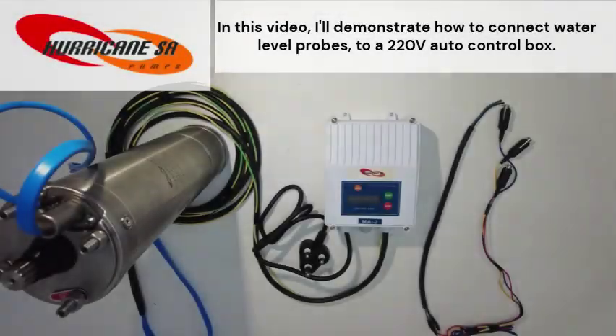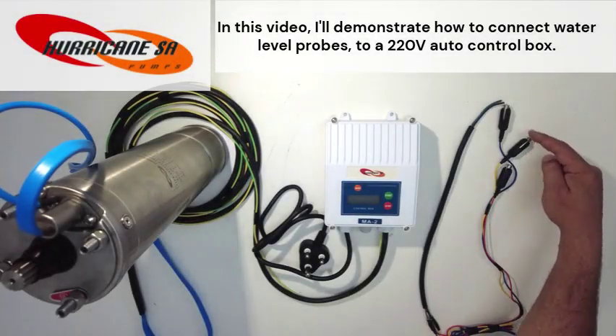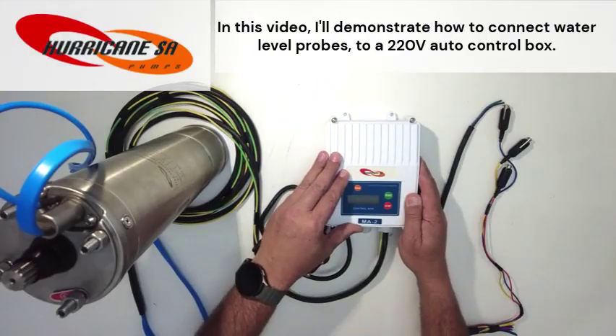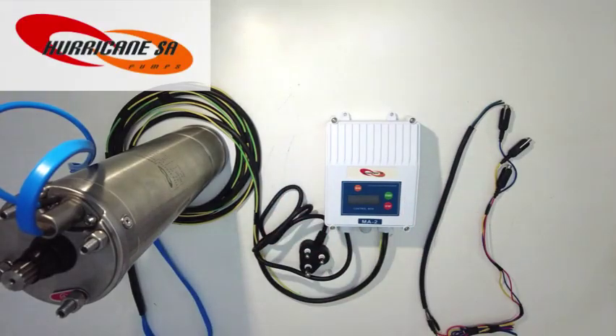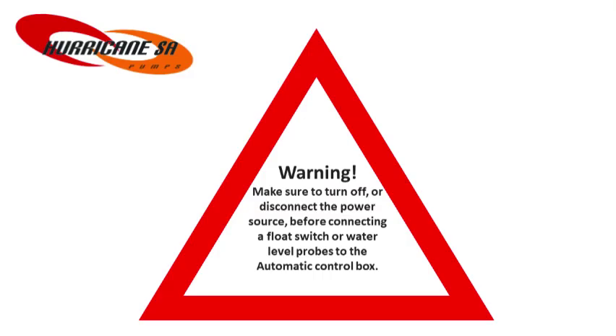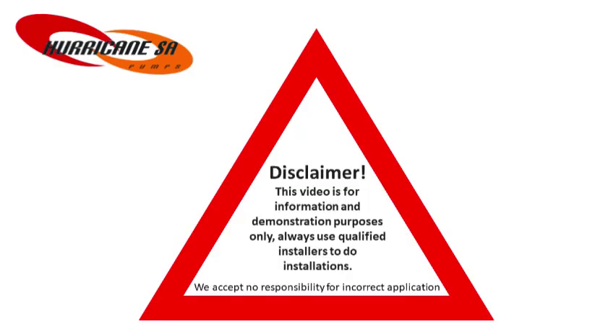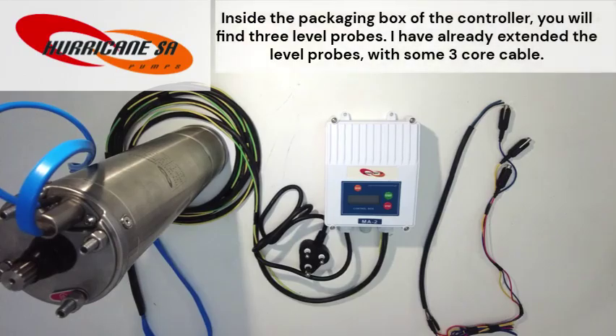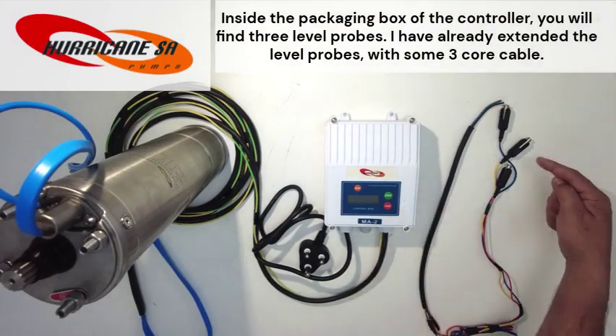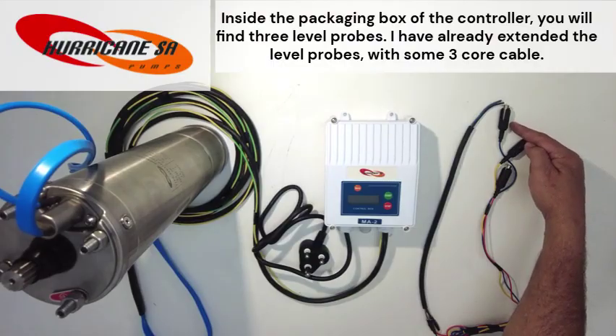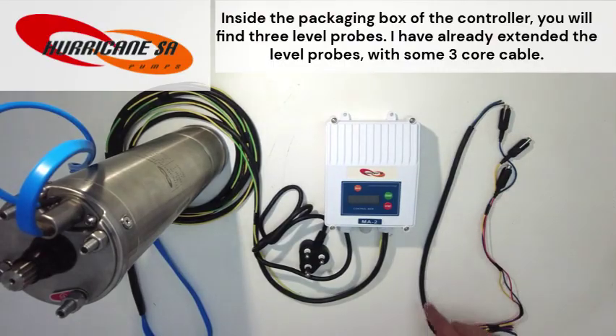In this video, I'll demonstrate how to connect water level probes to a 220-volt auto control box. Warning: make sure to turn off or disconnect the power source before connecting a float switch or water level probes to the automatic control box. Inside the packaging box of the controller, you'll find 3 level probes. I have already extended the level probes with some 3-core cable.